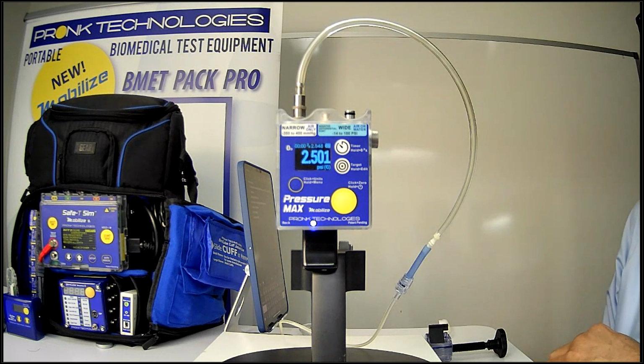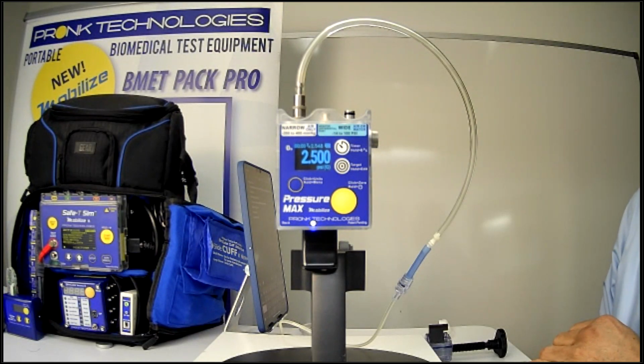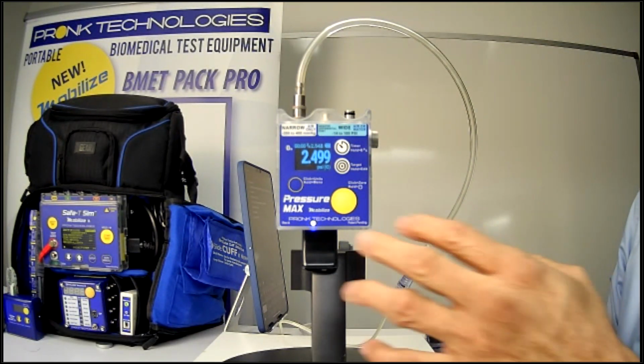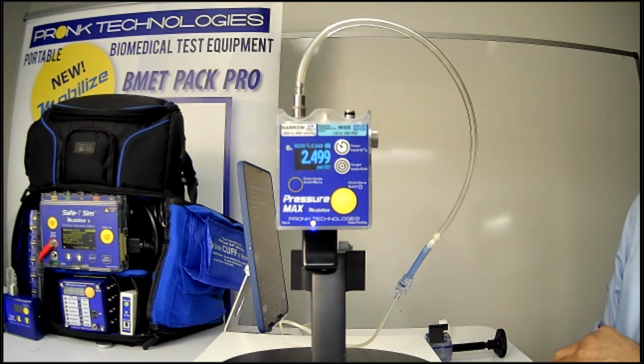The manifold is designed with an aluminum housing, with high grade enclosures and O-rings to ensure you have a solid seal so you don't have drift issues with your pressure measurements, because that only slows you down when you're trying to calibrate something if your pressure is always drifting because you have a small little leak in the system.